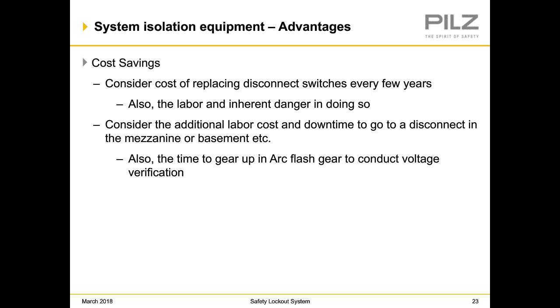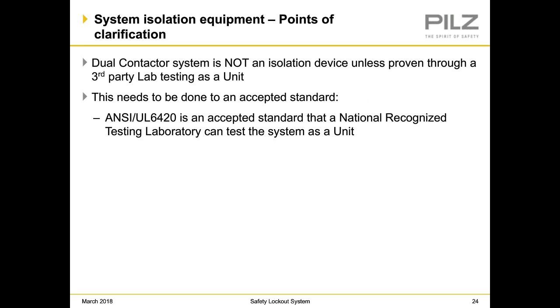So a dual contactor system is not an isolation device unless proven through third-party lab testing as a unit. So these are some points of clarification here, essentially. This needs to be done to an accepted standard, and UL 6420 is that standard. Now, some points of clarification, again, that I wanted to make on this is all the components that you saw in that panel that I showed previously, those are all readily available.